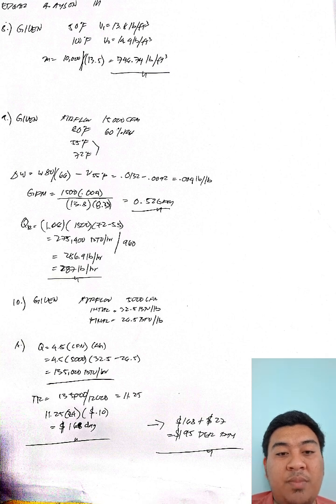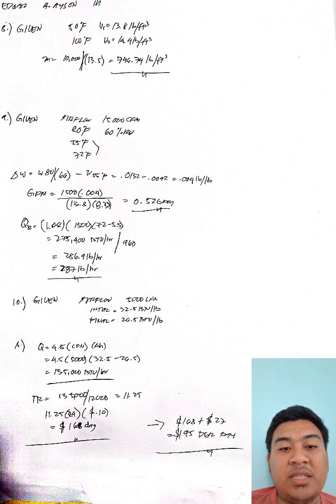So the solution is delta H, we just need to subtract 32.5 minus 26.5, then it is equal to 6 BTU per pound. Then total heat removed, we just follow the given formula, 4.5 times CFM of 5,000 times 6, which is equal to 135,000 BTU per hour. Then divide it by 12,000 to convert, then we have the value of 11.25 TR, or tons of refrigeration.